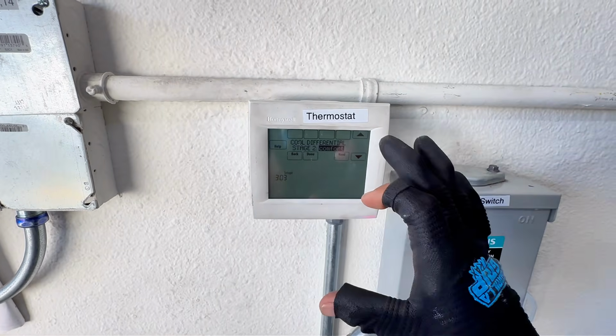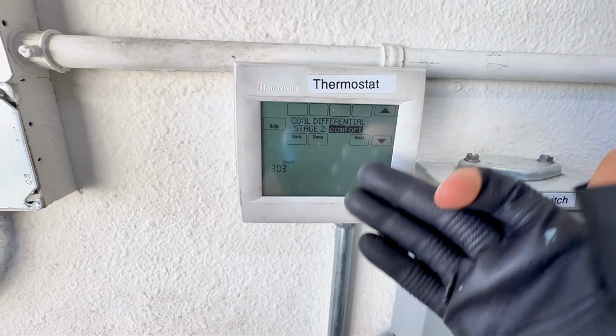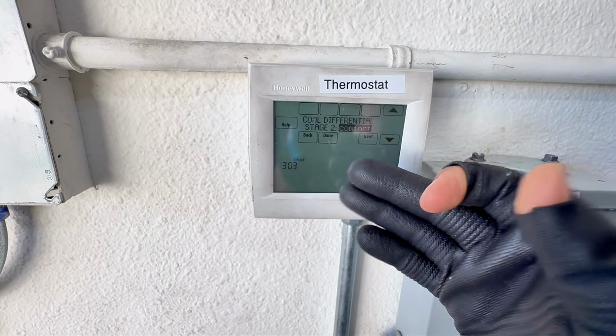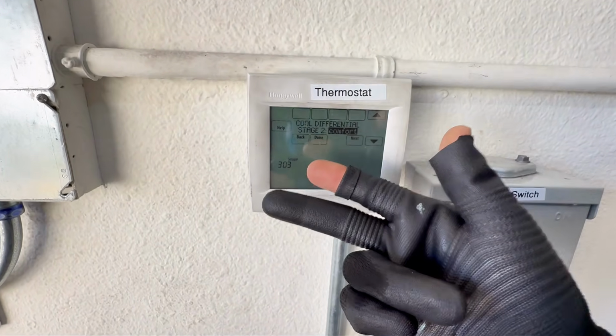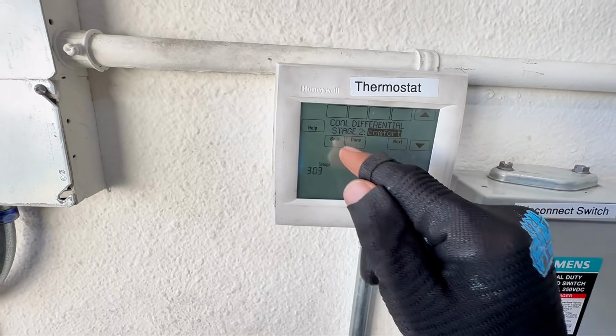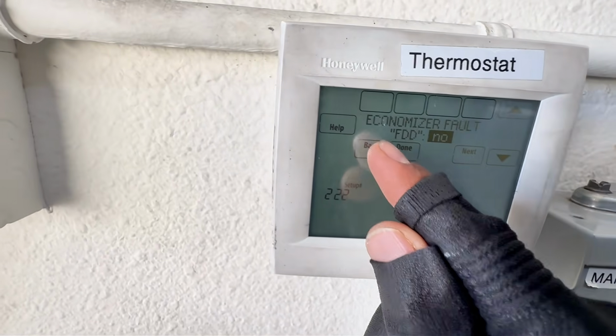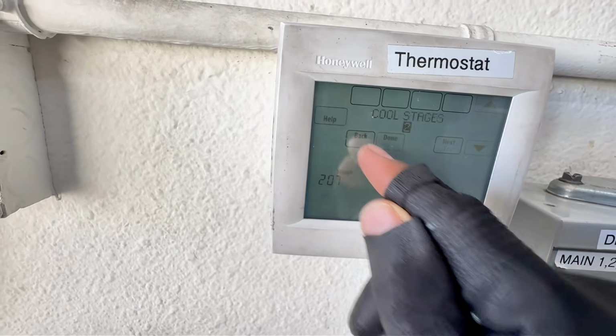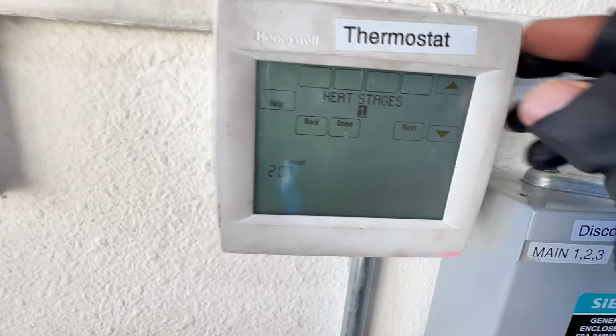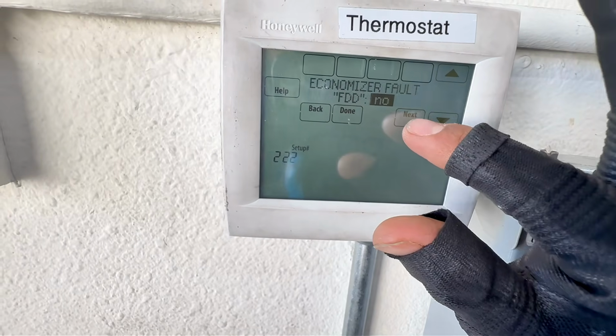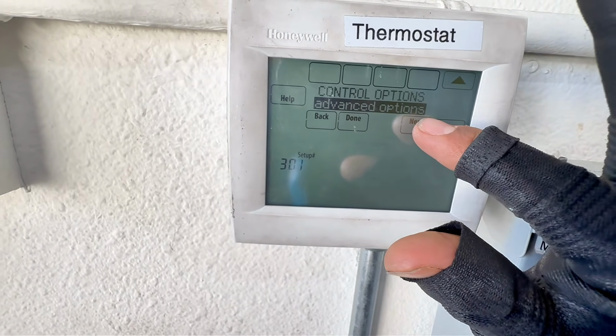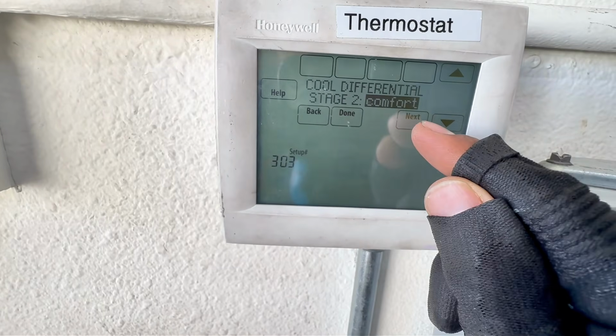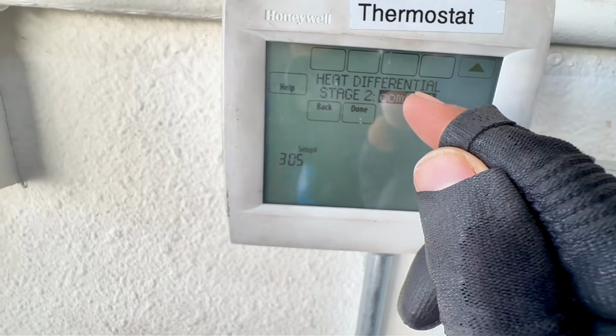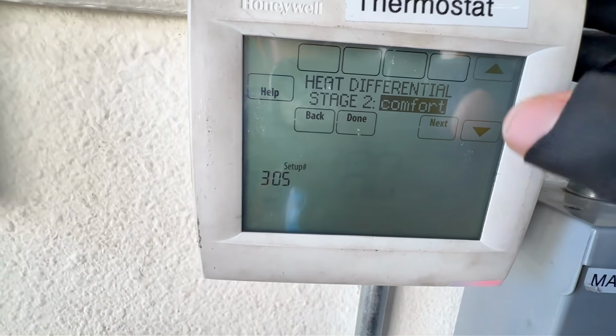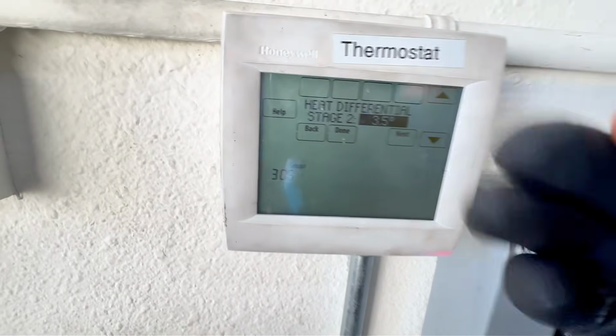But regardless of whatever thermostat you're working on, this is the idea. You're supposed to go to the settings behind it and make sure you put it to 2 stages of cooling, like in this case, or 2 stages of heating. If it's 2 stages of heating, this would be the same example. You would go to right here. Oops, no, don't cancel. Next, 2 stages of heating, put yes, next. Then you're going to see it right here: heat differential stage. Same concept as cooling, and you could put comfort or 3.5.